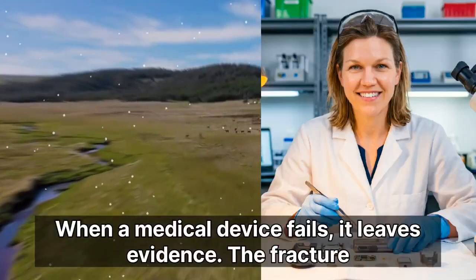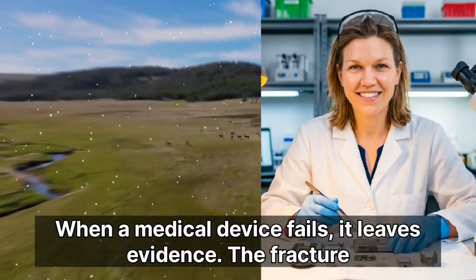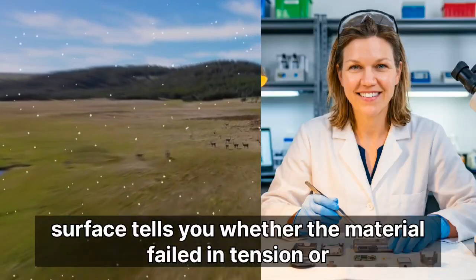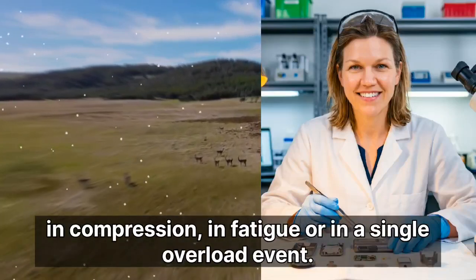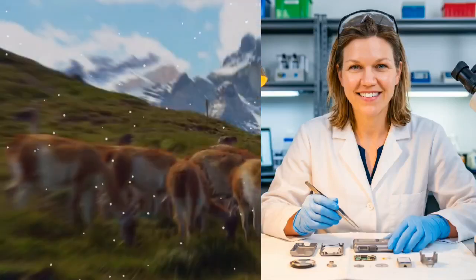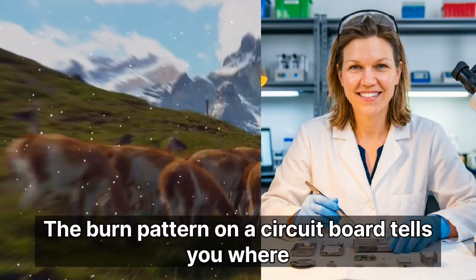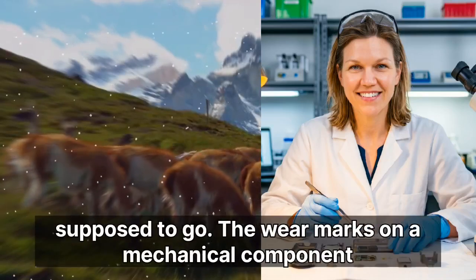When a medical device fails, it leaves evidence. The fracture surface tells you whether the material failed in tension or in compression, in fatigue or in a single overload event. The burn pattern on a circuit board tells you where the current went when it went somewhere it was not supposed to go.